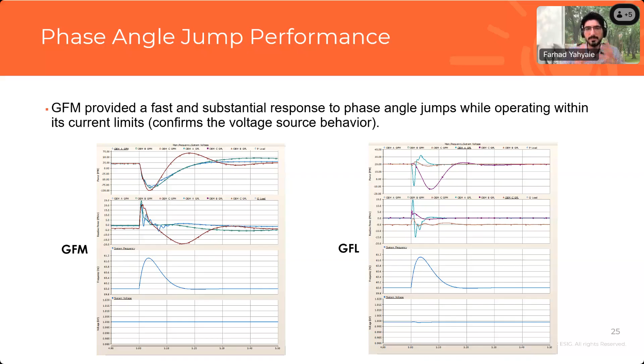Zooming into one of these phase angle jumps, like the 30-degree case, you can see a distinct behavior between GFM and GFL on the top plot, which shows active power. The GFM response is faster and more substantial to this phase angle jump, staying within the current limit, with the initial power around 20 megawatts or 20%. This confirms the voltage-source, synchronous-machine-like behavior of these machines.